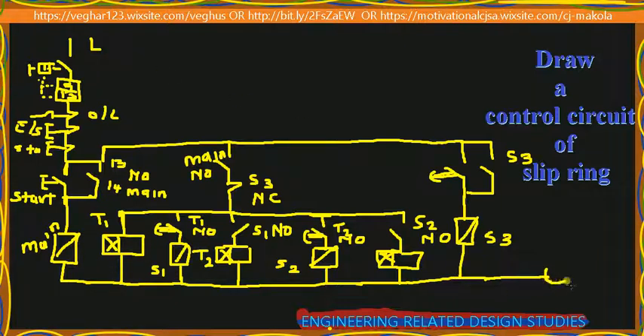And then this one connects to the neutral, depending on your coil, what size of your coil. So if your coil is 220V, use neutral. If it's 380V, use line to line. So this is normally open.